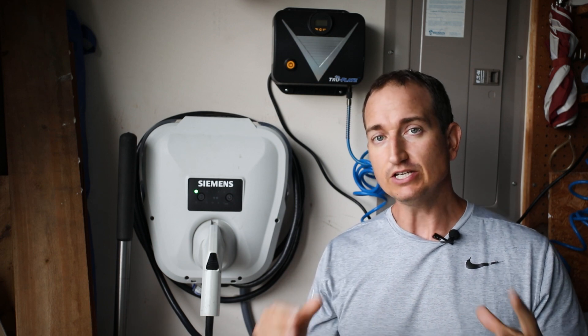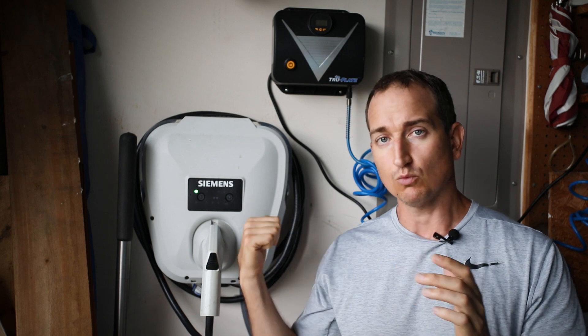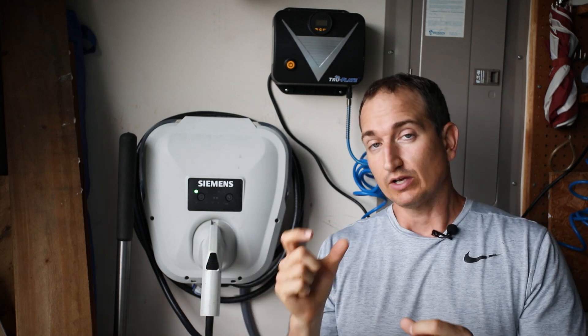From that point I wanted to know, why did this happen? Initially I thought it was a manufacturing defect. This was installed I think properly, but the problem looked to be right at the connection point where the installation wires, where the power comes from the house into the box itself.